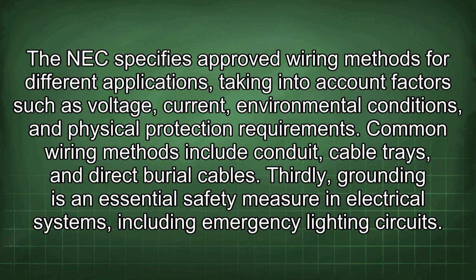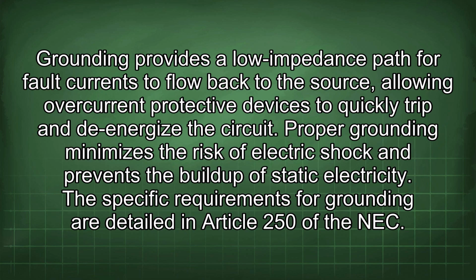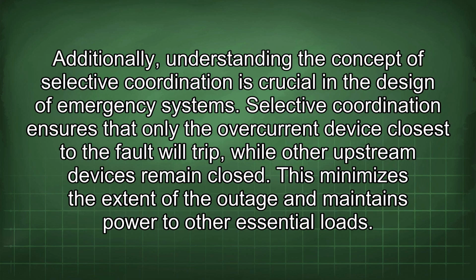Thirdly, grounding is an essential safety measure in electrical systems, including emergency lighting circuits. Grounding provides a low impedance path for fault currents to flow back to the source, allowing overcurrent protective devices to quickly trip and de-energize the circuit. Proper grounding minimizes the risk of electric shock and prevents the buildup of static electricity. The specific requirements for grounding are detailed in Article 250 of the NEC.